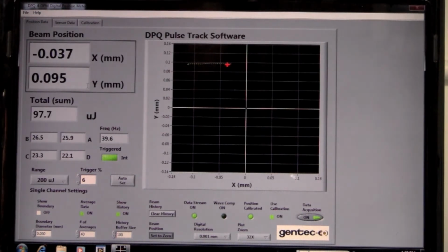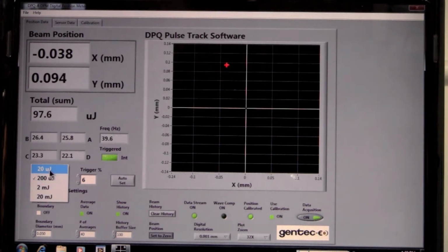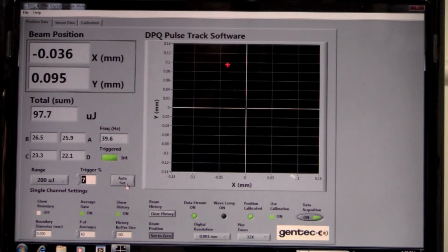Just below beam position, we can read the total pulse energy, which is the sum of energy of the 4 quad elements. To the right, there is a display of pulse frequency and also a trigger indicator. Next, we can see the instrument controls like range, trigger, and auto set. You can set the range from 20 microjoules to 20 millijoules. You can set the trigger from 2 to 20%. This brings us to the bottom of the screen, where there are a number of important software features that enhance the operation and use of the graphic XY display.